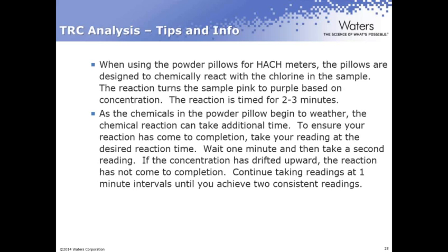So here's what I recommend you do. Take that reading, okay, wait 1 minute. Leave your sample in the cell in your meter. Wait a minute, and then take a second reading. See if that concentration has drifted upward. If that concentration has drifted upward, the reaction hasn't come to completion.